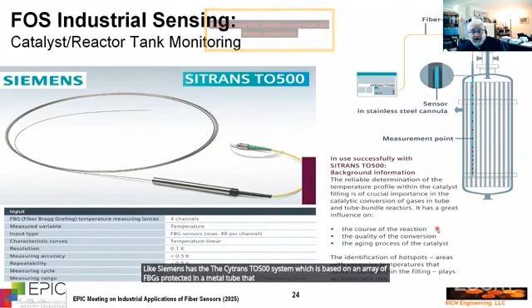In some heavy and petrochemical industries, there are distillation and cracking columns where it becomes necessary to know the temperature profile, control temperatures at specific points, avoid overheating, detect blockages, and avoid potential fires. Some solutions are already commercially available, like Siemens's Sitrans TO500 system, based on an array of FBGs protected in a metal tube that can be installed along boilers, tanks, and manifolds.